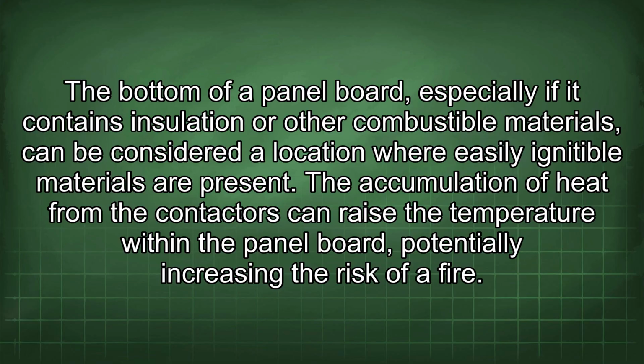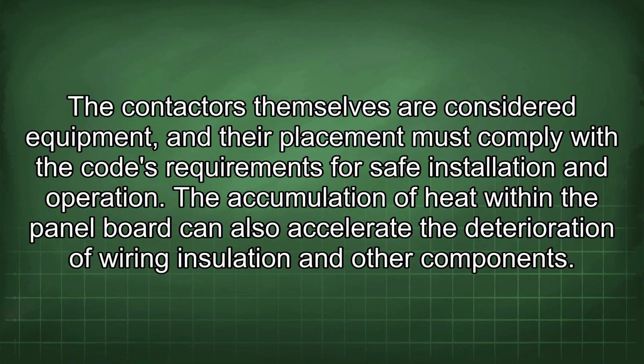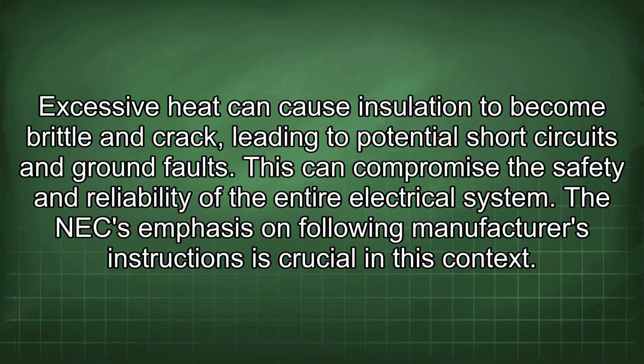The accumulation of heat from the contactors can raise the temperature within the panel board, potentially increasing the risk of a fire. The contactors themselves are considered equipment, and their placement must comply with the code's requirements for safe installation and operation. The accumulation of heat within the panel board can also accelerate the deterioration of wiring, insulation, and other components. Excessive heat can cause insulation to become brittle and crack, leading to potential short circuits and ground faults. This can compromise the safety and reliability of the entire electrical system.